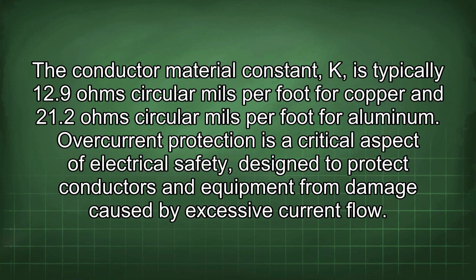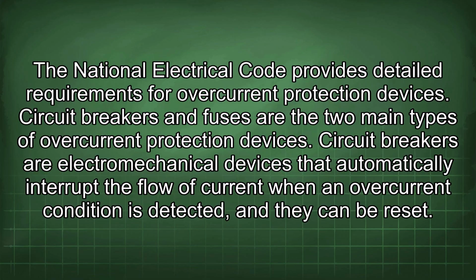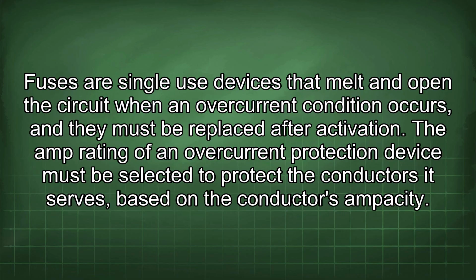Overcurrent protection is a critical aspect of electrical safety, designed to protect conductors and equipment from damage caused by excessive current flow. The National Electrical Code provides detailed requirements for overcurrent protection devices. Circuit breakers and fuses are the two main types of overcurrent protection devices. Circuit breakers are electromechanical devices that automatically interrupt the flow of current when an overcurrent condition is detected, and they can be reset. Fuses are single-use devices that melt and open the circuit when an overcurrent condition occurs, and they must be replaced after activation.